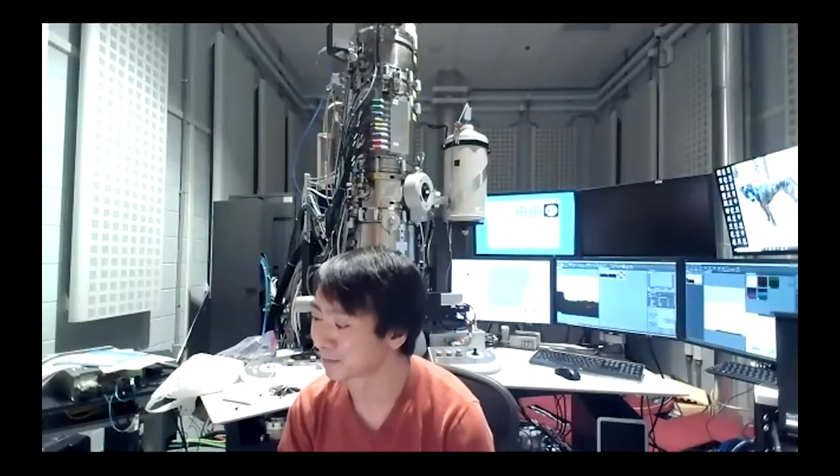My name is Toby Tong. I actually graduated from NC State and I've been with AIF since 2009. Behind me you can actually see the Thermo Fisher Titan. As Chris stated, it is an aberration-corrected scanning transmission electron microscope. What's really awesome about this tool is it has an aberration corrector on it — this piece right here — which allows us to obtain higher resolution imaging, like the tens-of-picometers resolution that Chris was alluding to, by taking into account small defects in the lens systems. Other institutions may have a Titan, but not all of them have the aberration corrector.